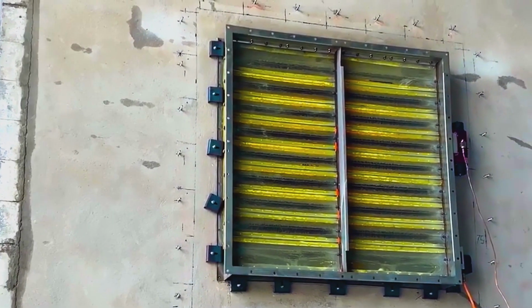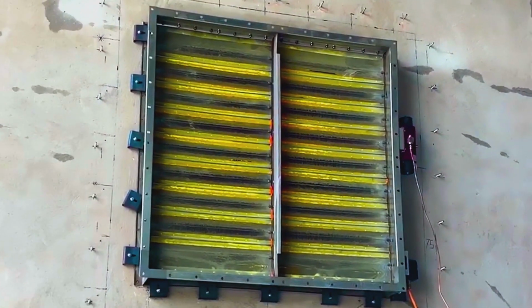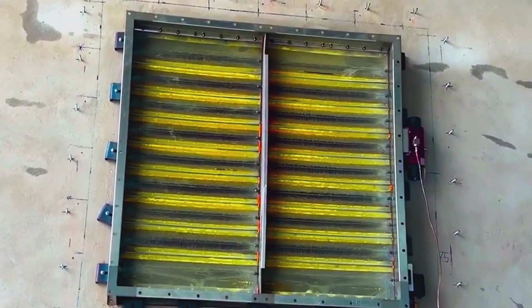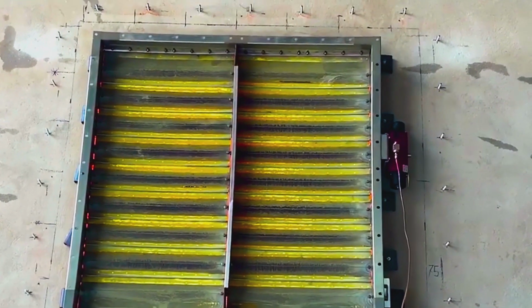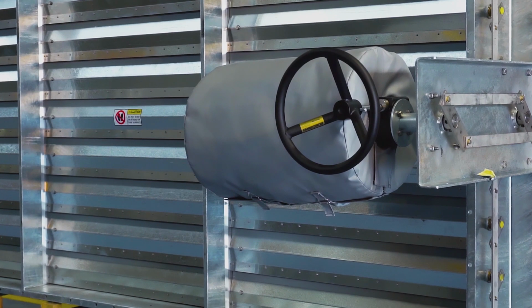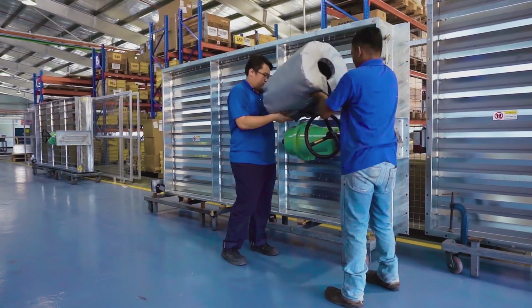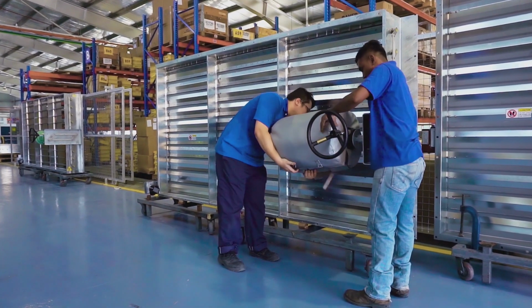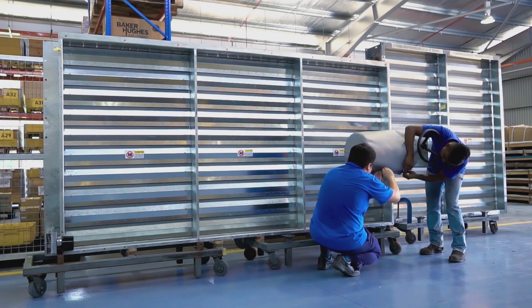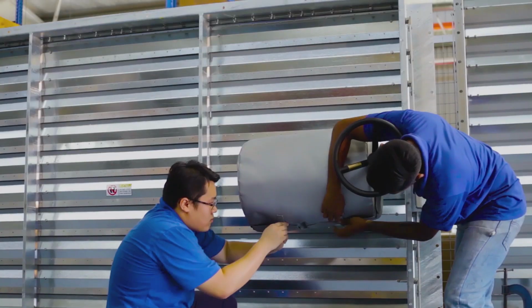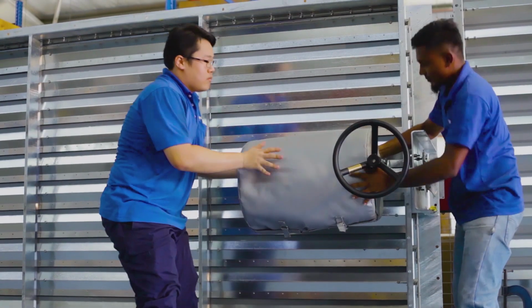Actuators are capable of continuing to operate the damper when subjected to temperatures of up to 400 degrees Celsius for 2 hours. Electric actuators are provided with a thermal jacket or insulated enclosure for such applications to ensure that the dampers continue to operate for smoke control purposes until the tunnel is fully evacuated.